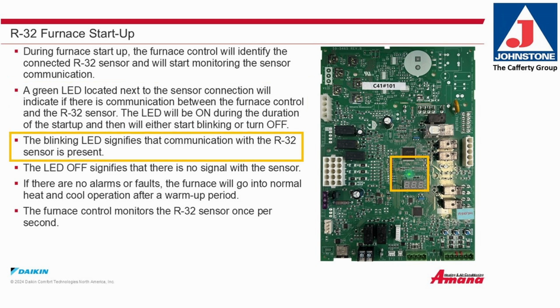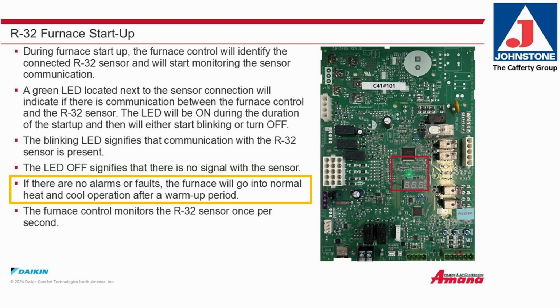The blinking LED signifies that communication with the R32 sensor is present. LED off signifies that there is no signal with the R32 sensor. If there are no alarms or faults, the furnace will go into normal heat or cool operation after a warm-up period. The furnace control monitors the R32 sensor once per second.